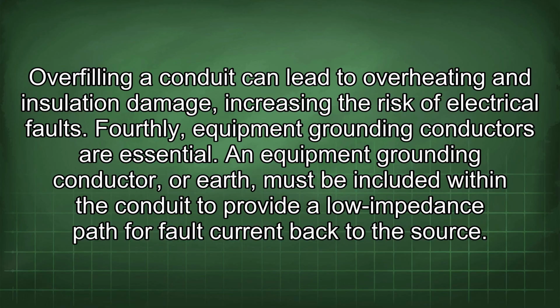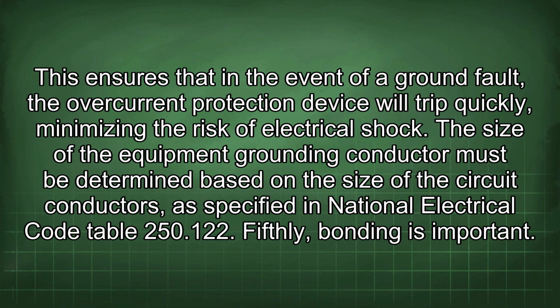Fourthly, equipment grounding conductors are essential. An equipment grounding conductor, or earth, must be included within the conduit to provide a low impedance path for fault current back to the source. This ensures that in the event of a ground fault, the overcurrent protection device will trip quickly, minimizing the risk of electrical shock. The size of the equipment grounding conductor must be determined based on the size of the circuit conductors, as specified in National Electrical Code Table 250.122.